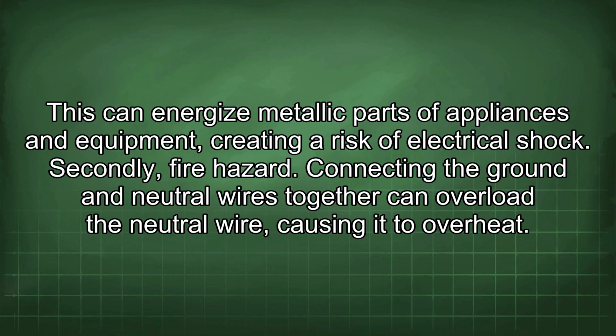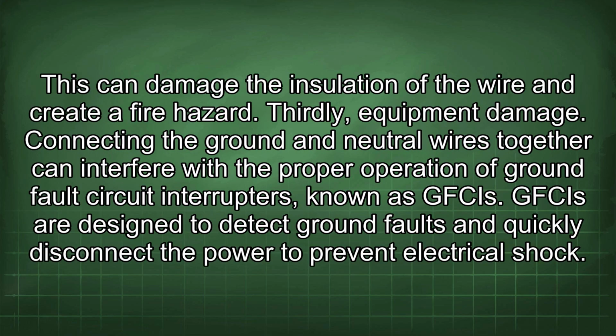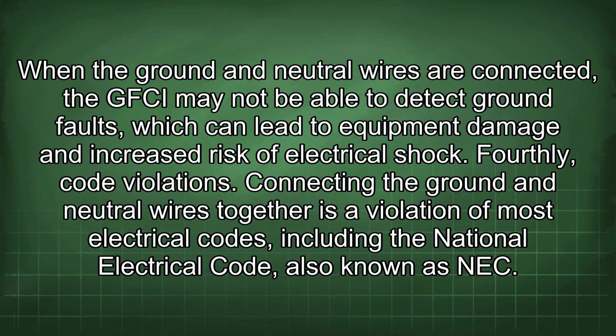Connecting the ground and neutral wires together can overload the neutral wire, causing it to overheat. This can damage the insulation of the wire and create a fire hazard. Thirdly, equipment damage. Connecting the ground and neutral wires together can interfere with the proper operation of ground fault circuit interrupters, known as GFCIs. GFCIs are designed to detect ground faults and quickly disconnect the power to prevent electrical shock. When the ground and neutral wires are connected, the GFCI may not be able to detect ground faults, which can lead to equipment damage and increased risk of electrical shock.